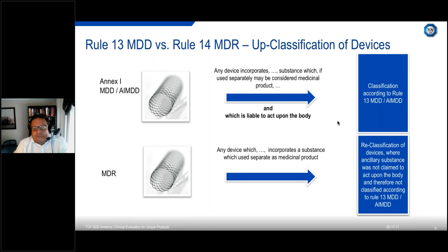Again, as I said, with the clinical data, there's no real difference between a medical device that incorporates a medicinal substance or not, because the manufacturer needs to have the clinical data and needs to demonstrate safety and performance of the device. And when it comes to equivalence, for example, if you have an uncoated and a coated version of your stent, coated with, let's just say, heparin, it would not be possible to claim equivalence between the coated and the uncoated version. Also, if you have different types of coatings or different medicinal products, let's say antibiotic-loaded bone cements with different antibiotic substances, it's not possible to claim equivalence between different devices with different medicinal products incorporated.